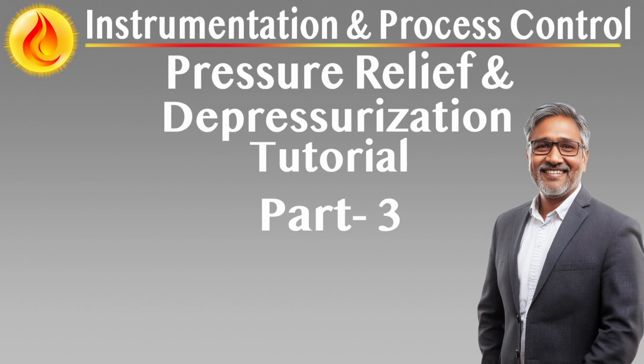To mitigate this, install heat tracing around the relief valve and associated piping. Ensure the heat tracing system is monitored and alarmed to detect loss of function. Consider chemical inhibition, e.g. methanol or glycol injection in hydrate-prone systems.